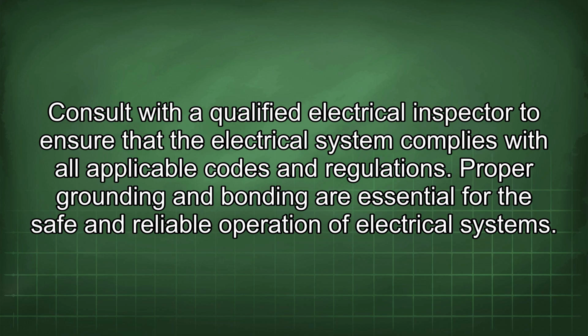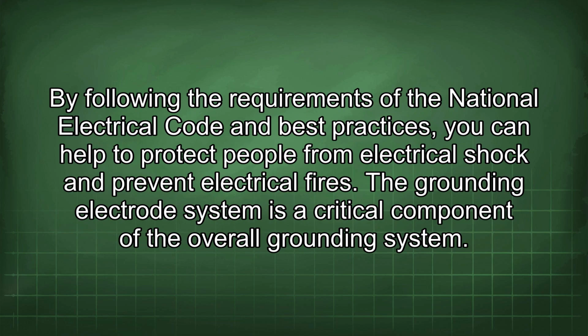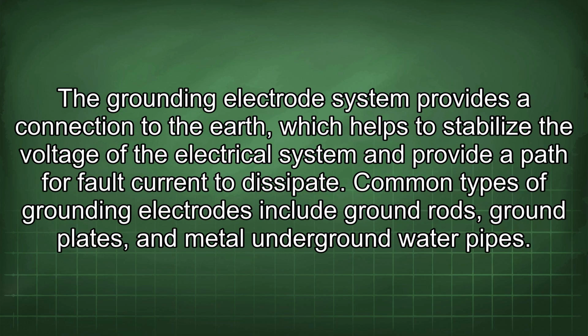Proper grounding and bonding are essential for the safe and reliable operation of electrical systems. By following the requirements of the National Electrical Code and best practices, you can help to protect people from electrical shock and prevent electrical fires. The grounding electrode system is a critical component of the overall grounding system. The grounding electrode system provides a connection to the earth which helps to stabilize the voltage of the electrical system and provide a path for fault current to dissipate. Common types of grounding electrodes include ground rods, ground plates, and metal underground water pipes.